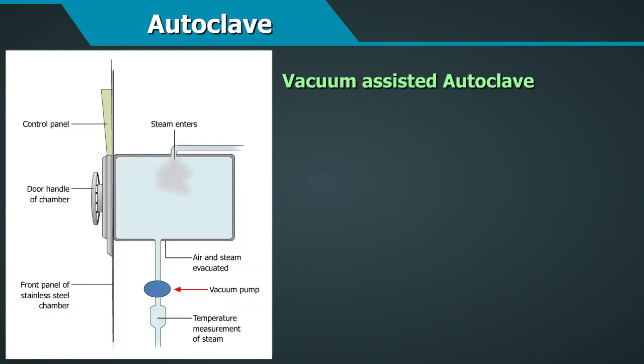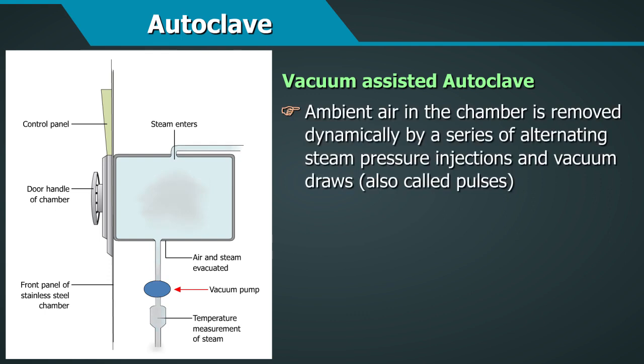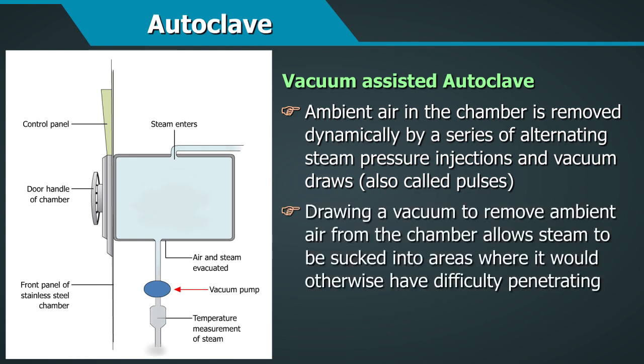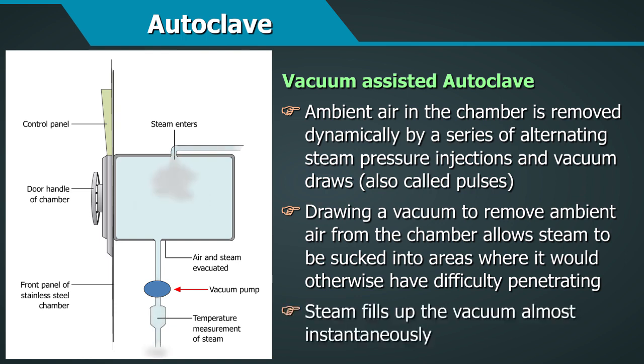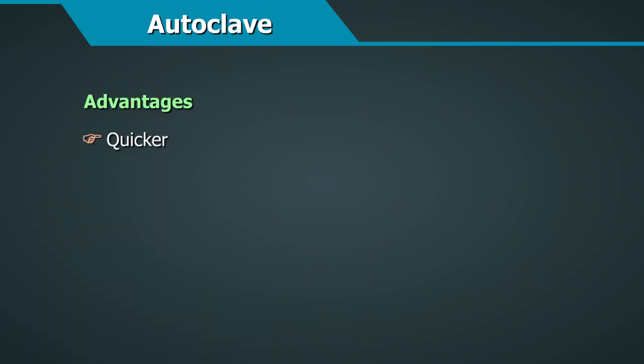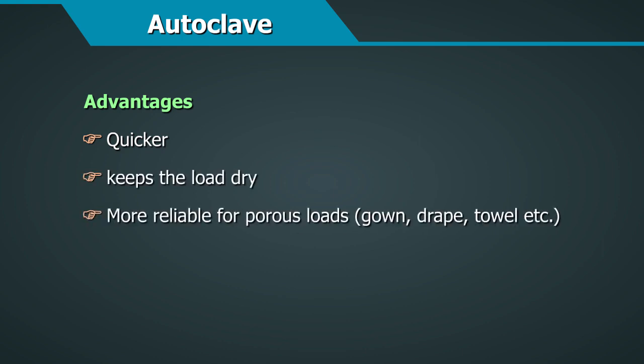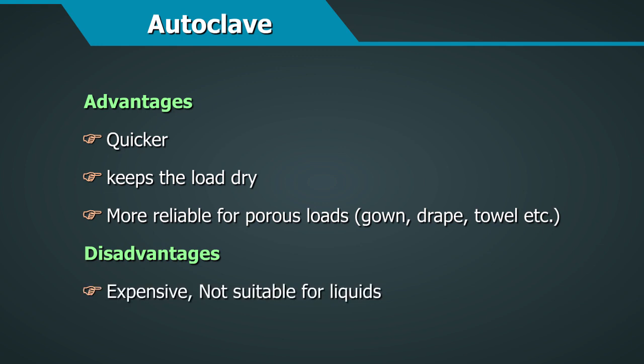Vacuum-assisted autoclave. The ambient air in the chamber is removed dynamically by a series of alternating steam pressure injections and vacuum draws, also called pulses. Drawing a vacuum to remove ambient air from the chamber allows the steam to be sucked into areas where it would otherwise have difficulty penetrating. Steam fills up the vacuum almost instantaneously. Advantages: it's quicker and keeps the load dry. It is a more reliable method for porous loads such as gowns, drapes, towels, etc. Disadvantages: it is an expensive method and not suitable for liquids.